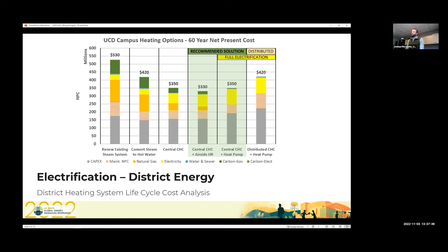What we've done already—this is a summary of why hot water is the pathway to clean energy for us. It's an opportunity to ultimately get off our gas-fired boilers and our steam system. We've begun converting; I'll show you the scope of what we've done so far. The next step is to put in the heat recovery chillers and add more buildings to our hot water network. Full electrification will then require more low-grade heat source in the winter, which we've done a study on as well.